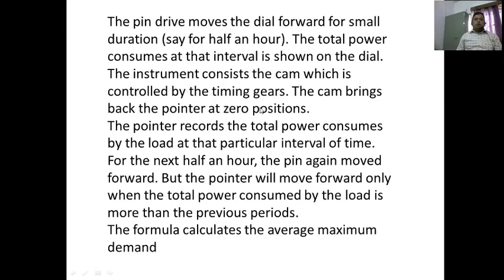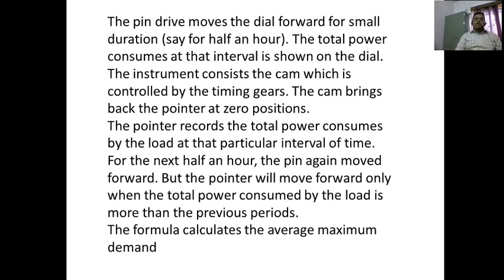The cam brings the pointer to zero position, and the pointer records the total power consumed by the load at a particular interval of time. For the next half an hour, the pin again moves forward but the pointer will move forward only when the total power consumed by the load is more than the previous period. The average maximum demand and maximum demand are essential to calculate the load on the particular consumer — how much load is being used, what is the tariff. The maximum demand indicator is very useful in utility companies.